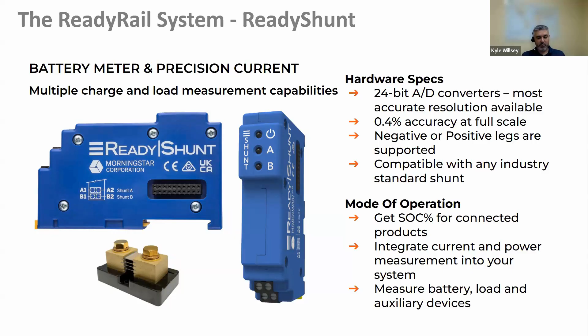The one thing this really brings to a system that didn't exist before is the ability to use the shunt in a net sense to measure energy in and out of the battery bus. That can be used to determine an actual accurate state of charge for a given battery bank, in percentage terms as opposed to just a voltage-based approximation. It's a really powerful tool, especially paired with the Ready Relay. You now have control and measurement all in one package.